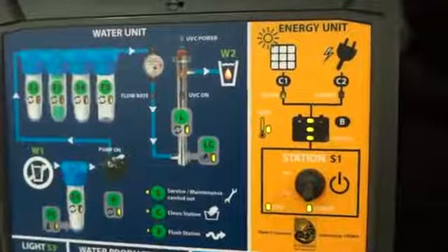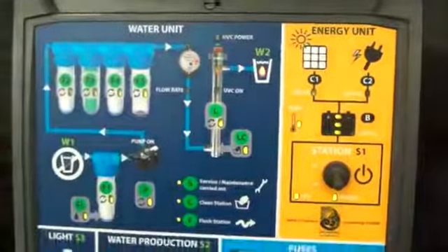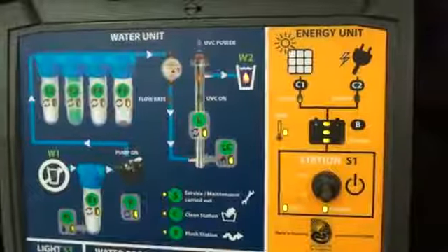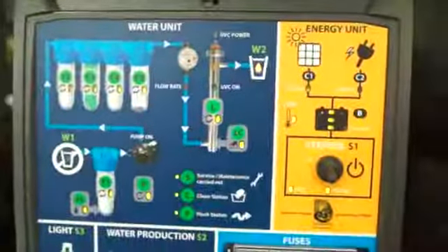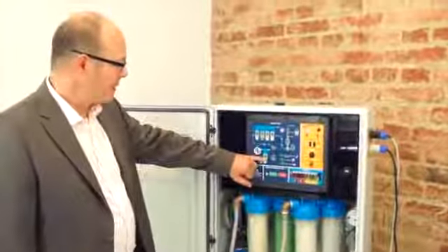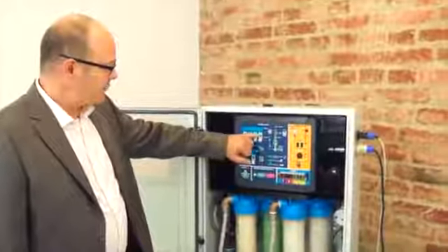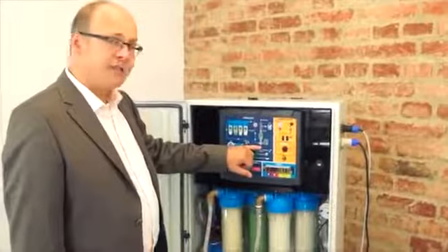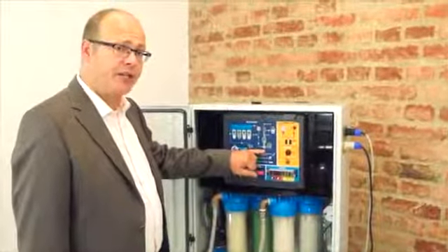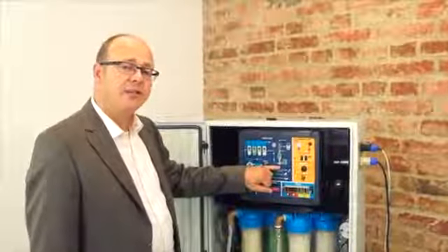The display unit cooperates with the user. That means if the filter is not okay, the display will indicate orange initially and then red. The same is true for the other filters, but especially the disinfection unit has some additional safety features. Should it not work, the machine won't even start, and the display will indicate to the user that care according to the manual is required in order to have a stable supply of water.